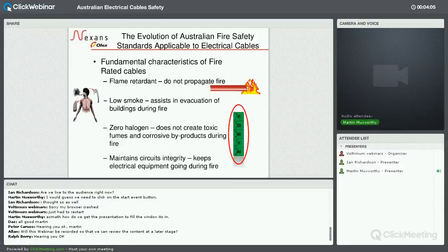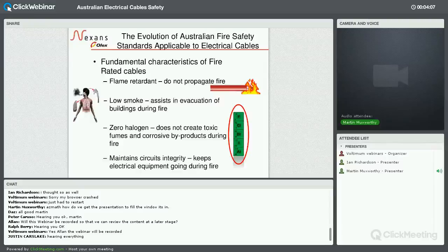The next one is that they don't produce a lot of smoke, and I guess that's fairly obvious. That assists in getting people out of buildings if there is a fire. Zero halogen. This may not be quite so obvious, but halogens are a specific group of elements that create a lot of toxic fumes and corrosive byproducts when they're burnt. So halogens are something that we try to eliminate from fire-rated cables.